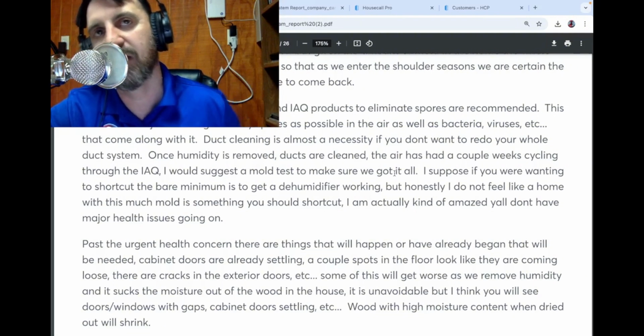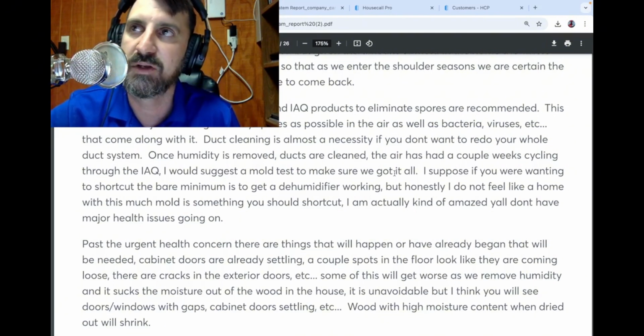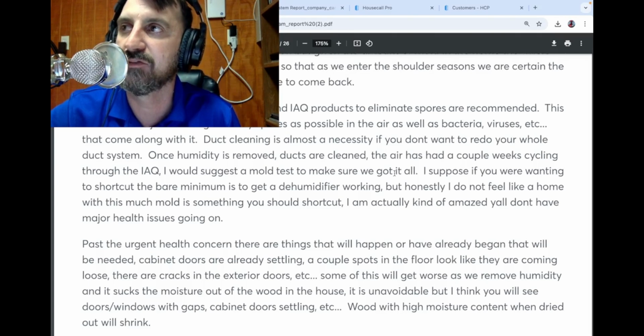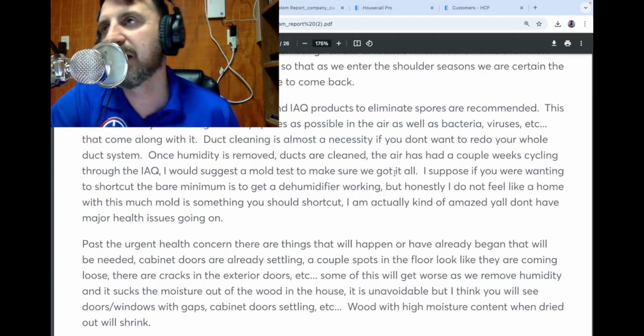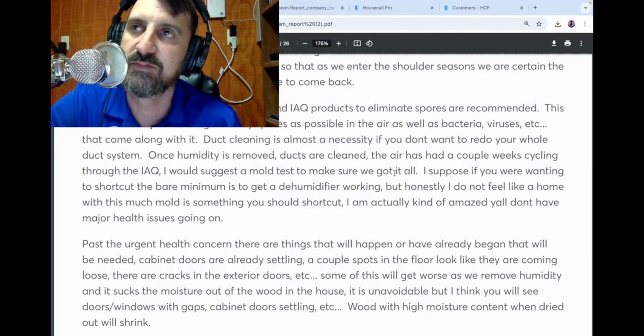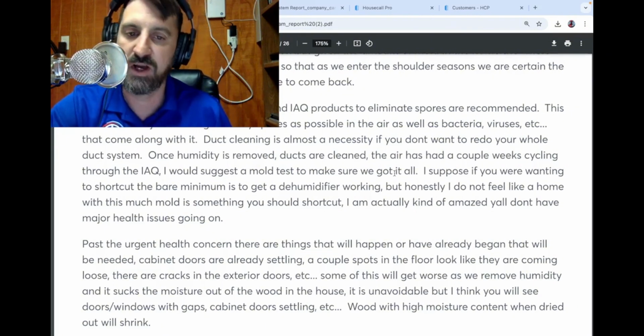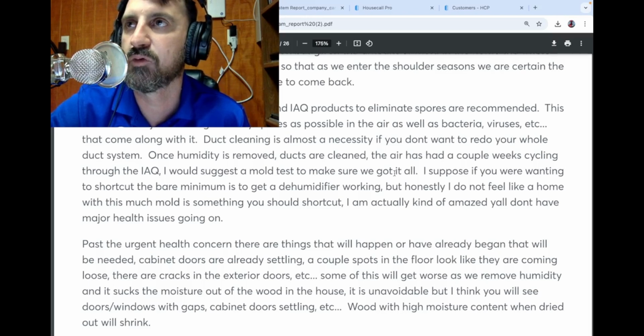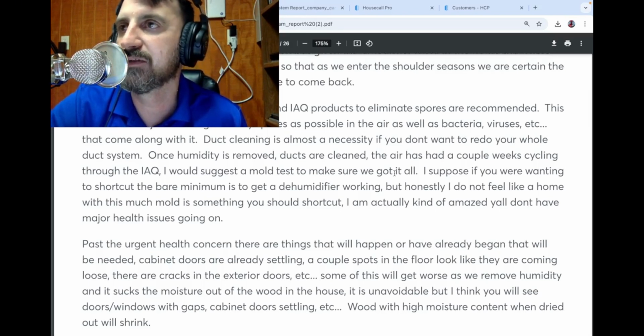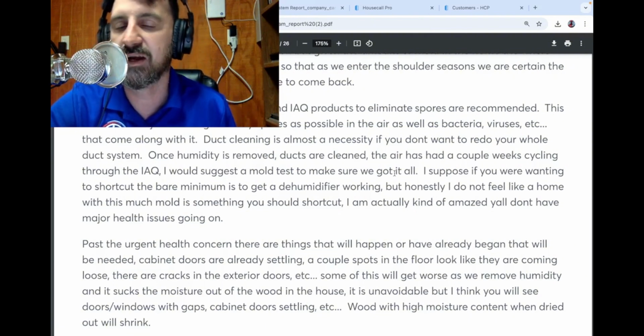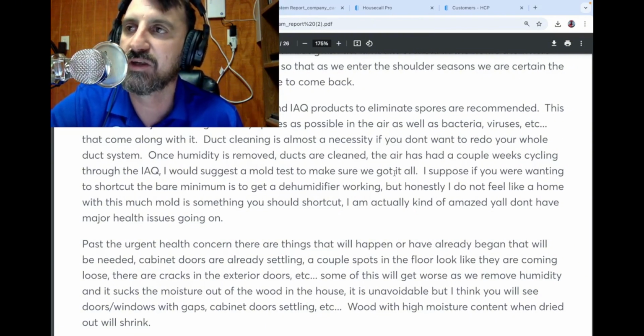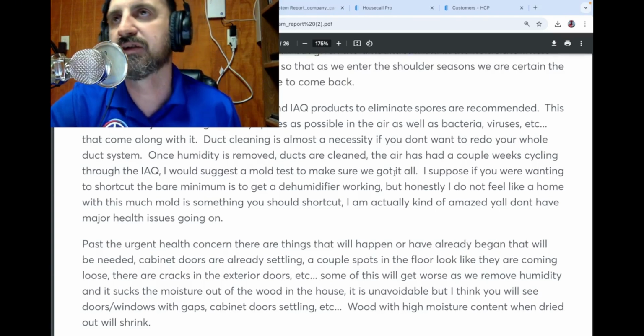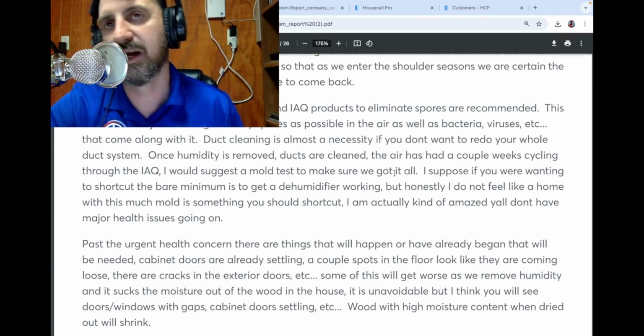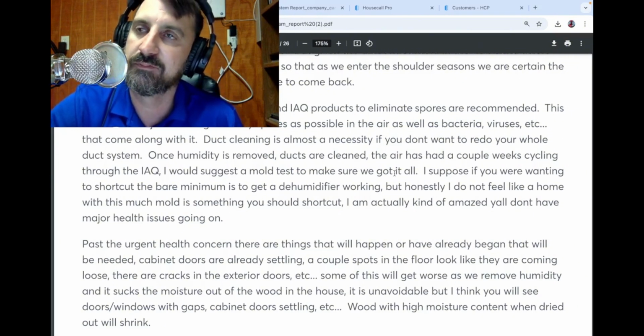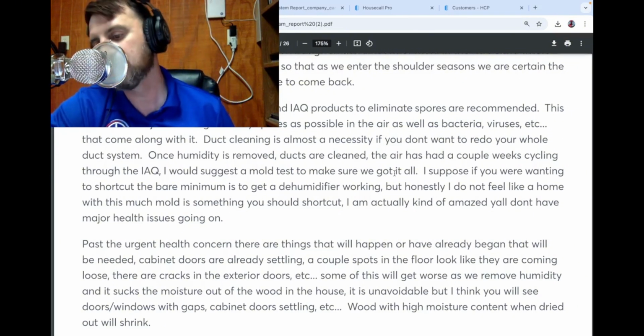Obviously, you want to put your filter at your unit when using these. I mean, you don't have to, but it keeps all of that stuff from getting to your coil. And then on the wet side of your coil, you want to put a UV light. The wet side of that coil is providing an area for mold and bacteria and sludge and stuff to build. And putting a UV light there not only helps kill off that stuff in the air that's passing through it, but it'll keep your drain from stopping up as often because it really doesn't give it any material to get washed down in there. And then on the supply end of that, you put an air scrubber with a UV light.